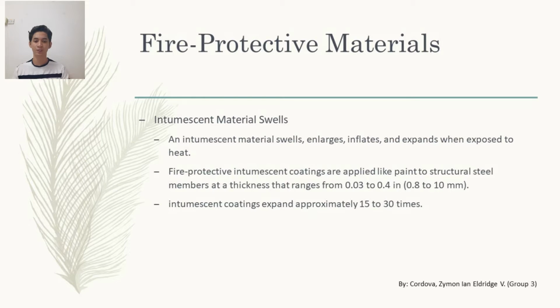An intumescent material enlarges, inflates, and expands when exposed to heat. Fire protective intumescent coatings are applied as paint to structural steel members at a thickness that ranges from 0.03 to 0.4 inches, or in millimeters, 0.8 to 10. Intumescent coatings expand approximately 15 to 30 times.